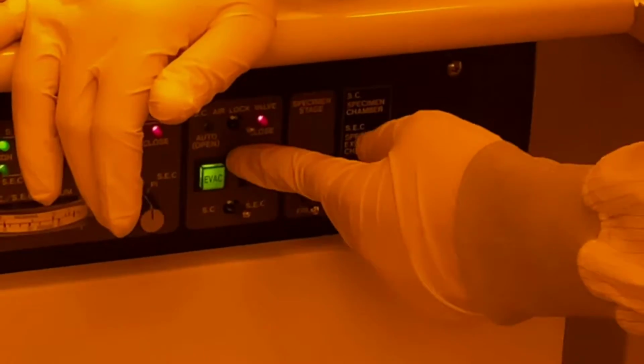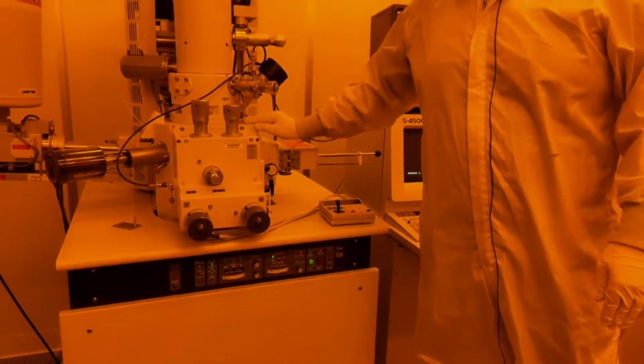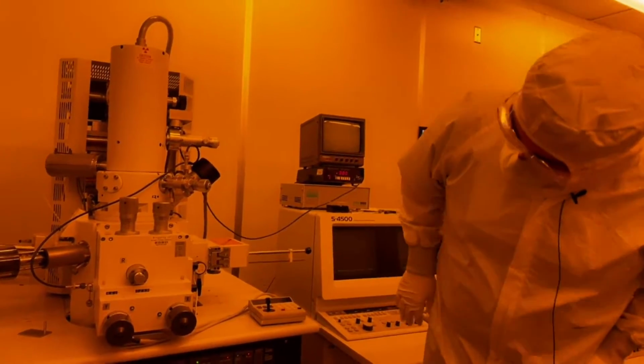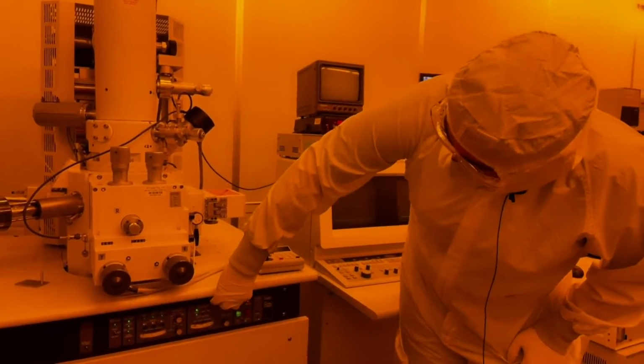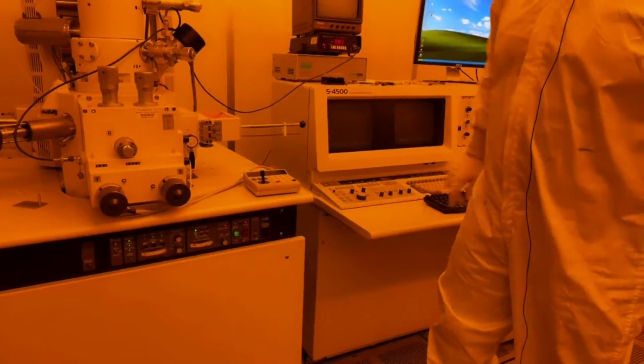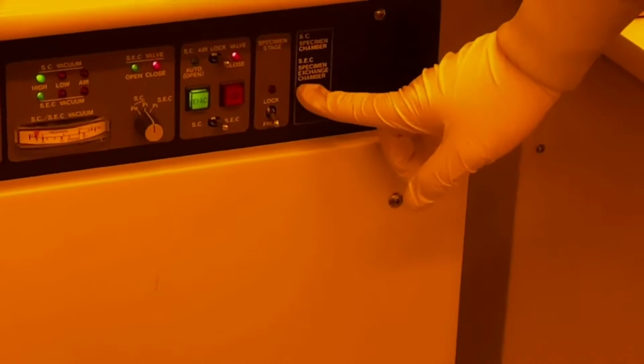Additionally, you have an airlock. While you're not using the system, the airlock should always be closed to ensure the safety of and vacuum of the main chamber. While you're using it, this will have to be open. So that is an interlock that prevents the gun from turning on when the airlock is closed. Finally, you have a stage lock. This can prevent any mechanical vibrations that may exist in the system and can get you a better image if that's happening.